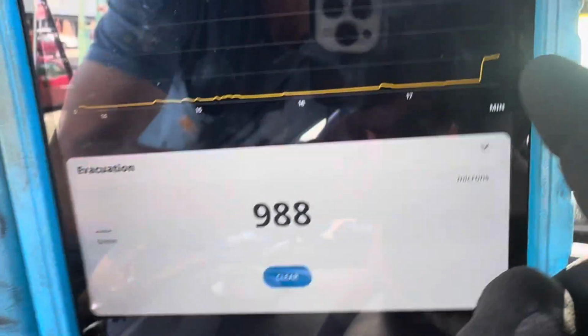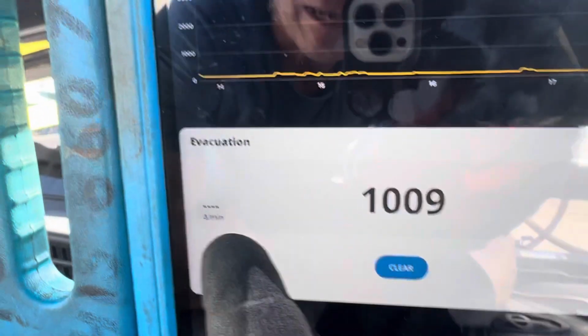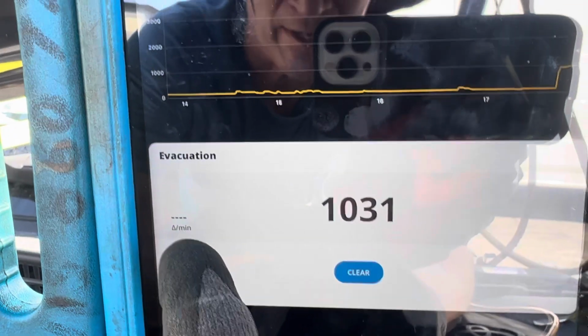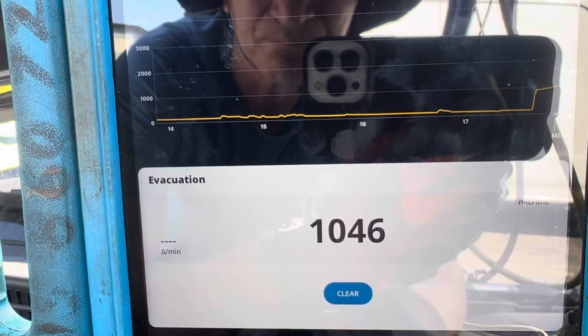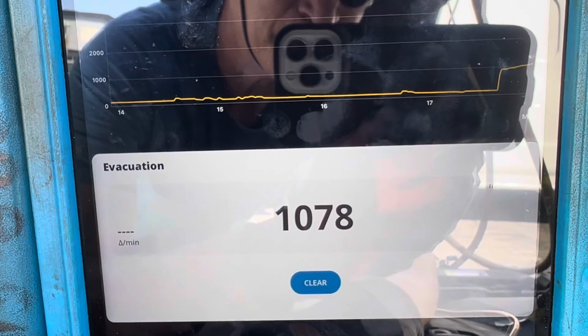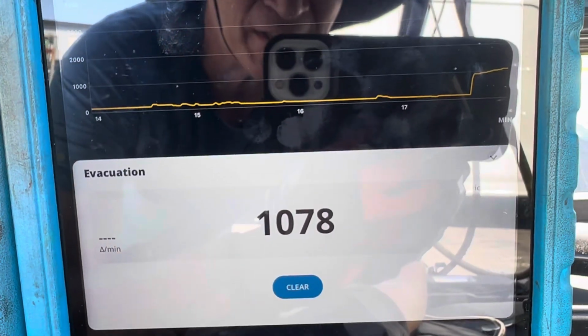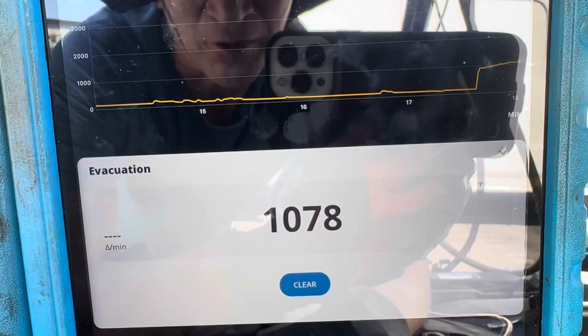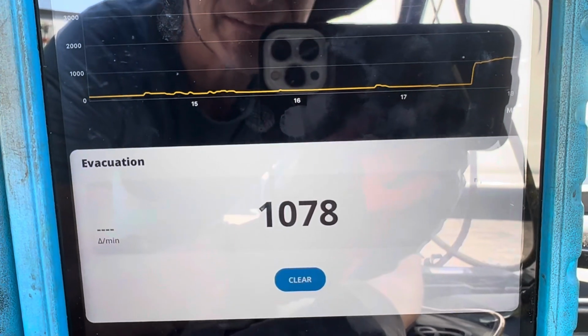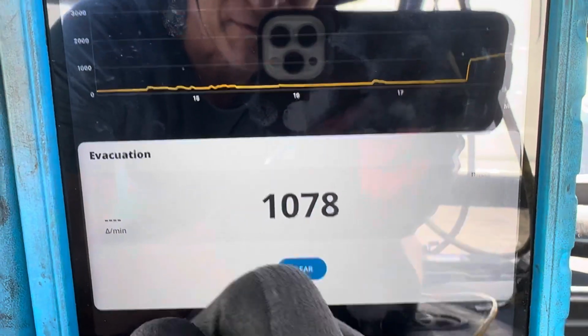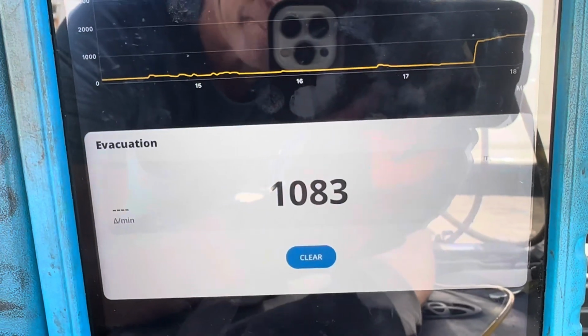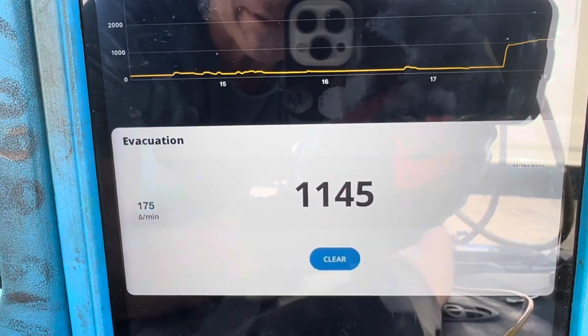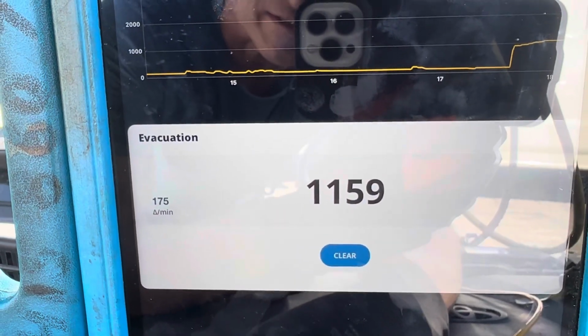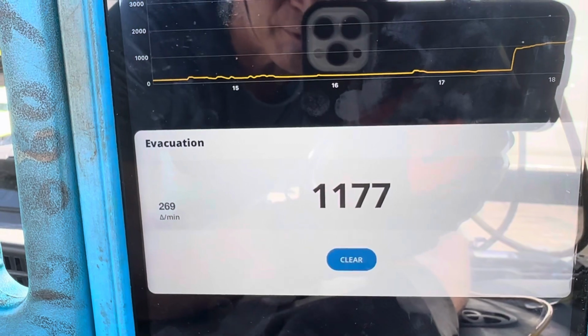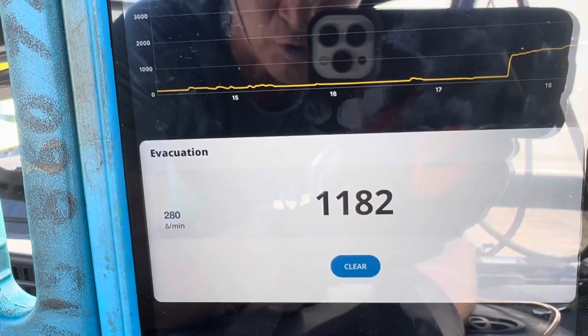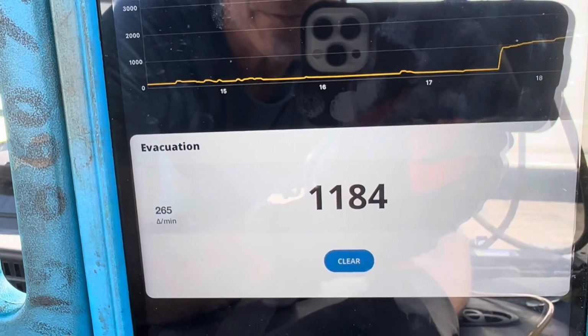If you look over here, after a while it'll calculate the rise after a few minutes. I'm saying 1,500 microns, maybe I'm wrong, maybe it'll be a little less, because I only vacuumed it for a certain time. This all depends on the ambient conditions, the type of oil in the system, and how long it was exposed to moisture. This was open for several days.